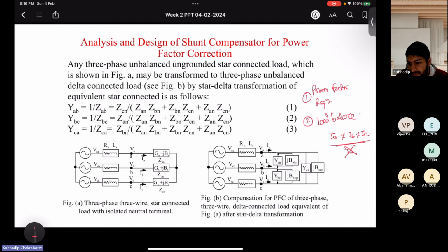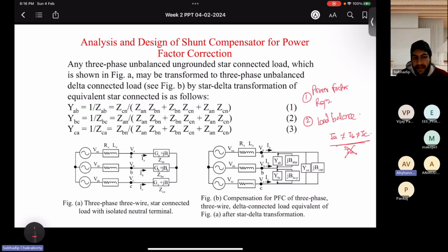If you break it down using Fortescue, that is the symmetrical components, positive sequence, negative sequence, and zero sequence, will there exist negative sequence? Because these are unbalanced currents. Yes, negative sequence currents will exist even in three-phase, three-wire systems.